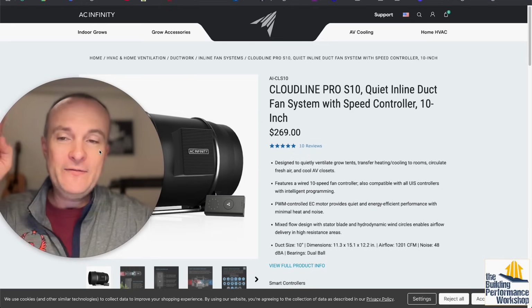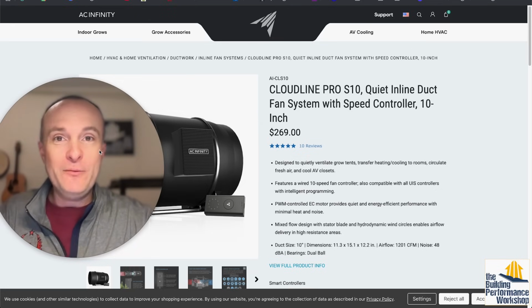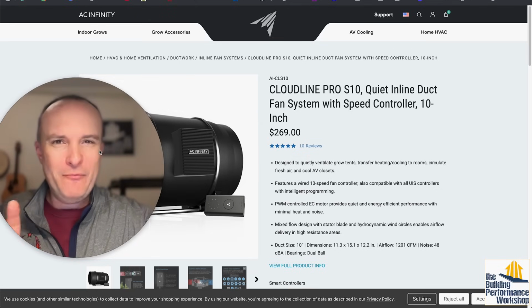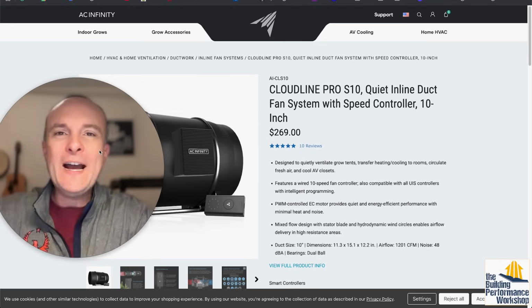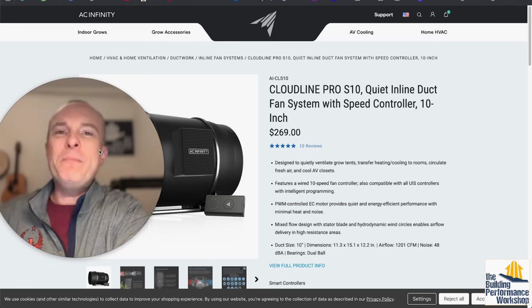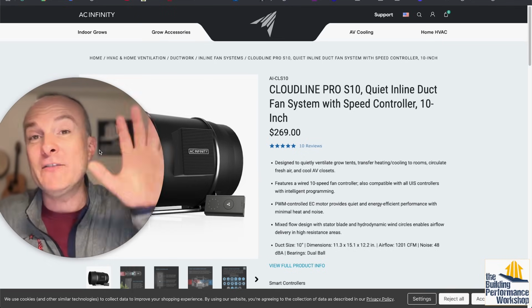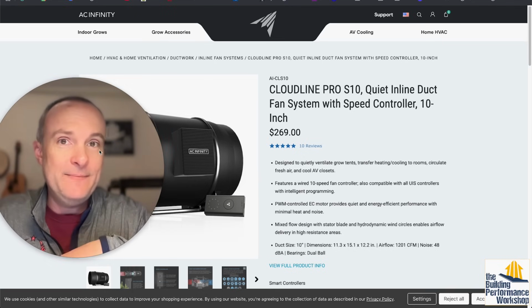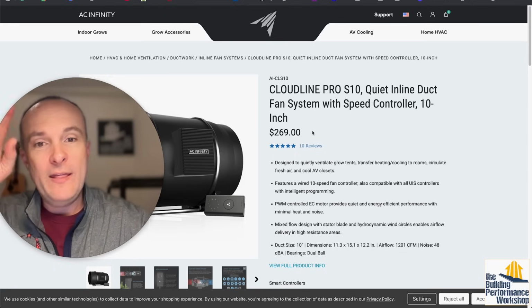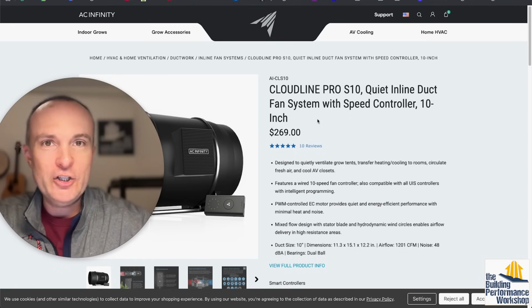What we need to do is figure out the 1 air-cycle-per-hour rate and aim for that, so every hour the air passes by the dehumidifier and the ERV—that's volume divided by 60. So a fan rated at 1200 CFM would be outlandishly big for this.